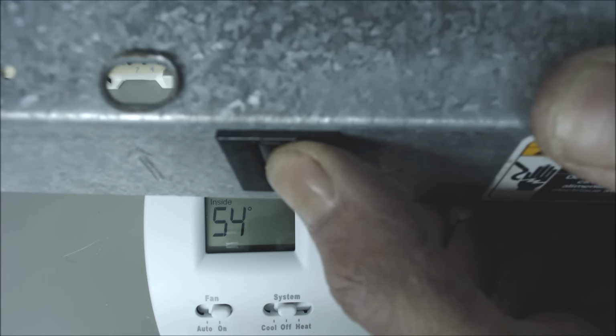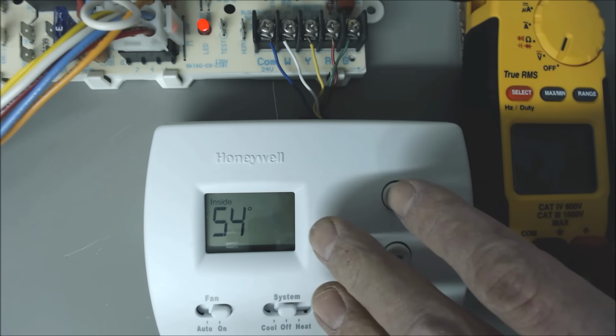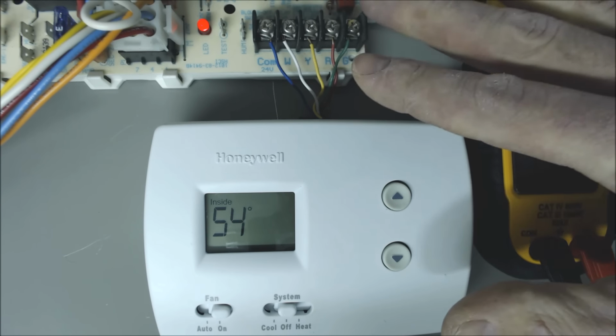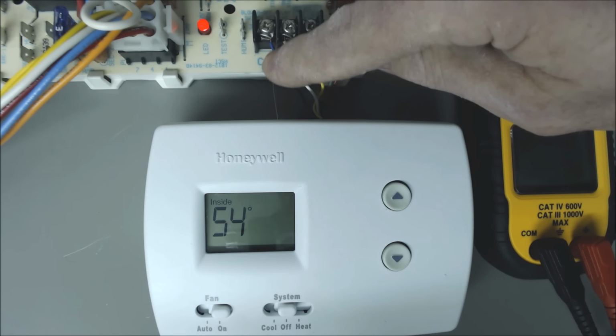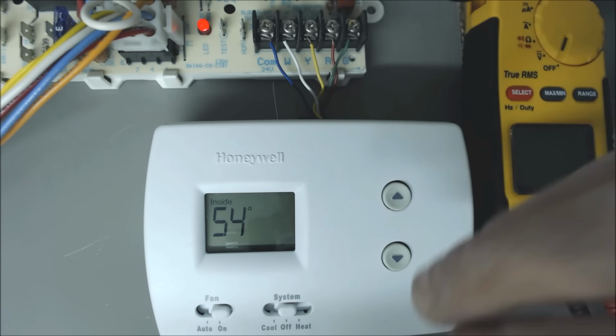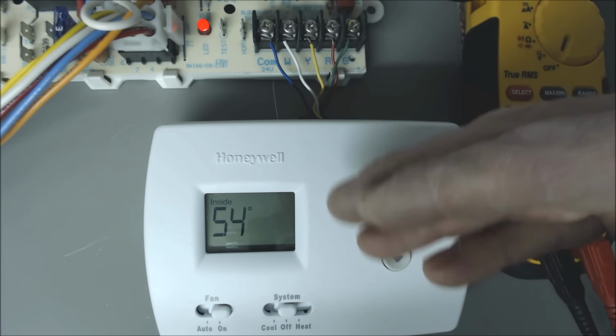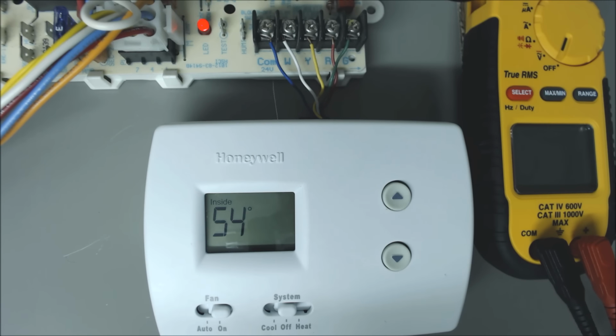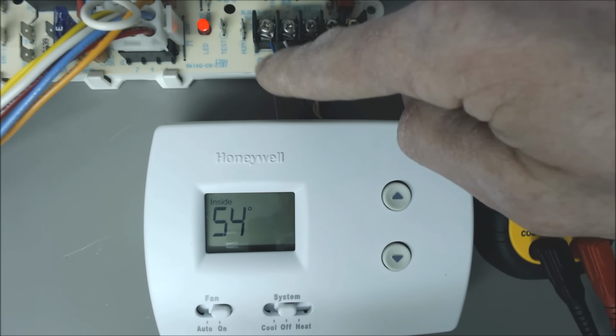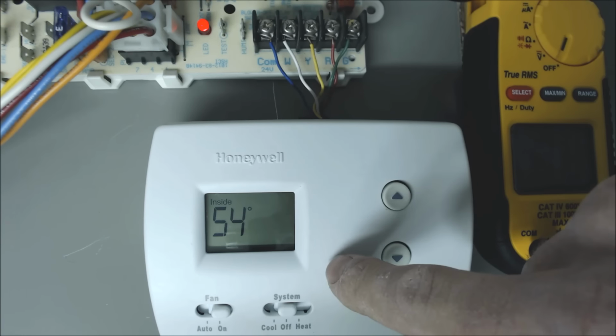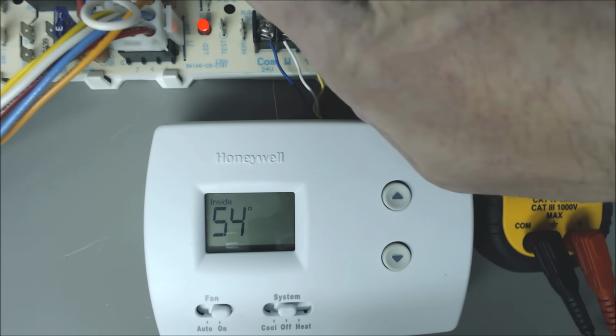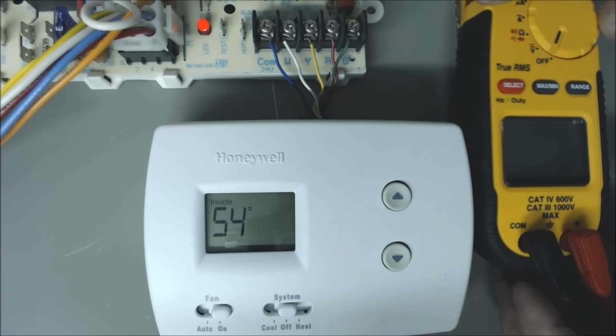If you're in the furnace, you just want to make sure that you have this door switch shut in order to make sure that you have power to the thermostat. In order to do these tests, it's not necessary to actually have a C wire going to the thermostat. If your thermostat is battery operated or is a non-digital thermostat, then you do not need this C wire coming from C to C in the thermostat. However, our C terminal right here is actually connected to the transformer. So we can actually take a voltage reading right now.